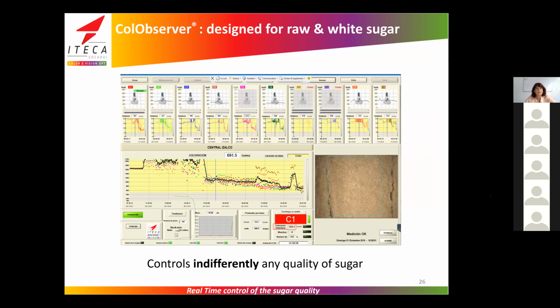The ColObserver is designed for raw and white sugar. We can configure different alarm thresholds and set points according to the sugar quality. For instance, we can set the correlation equation for each sugar quality with different range of color and use the one corresponding to the ongoing quality produced. In this case, C9 average color between 600 and 750 ICUMSA units could as well be 30 ICUMSA units and 1,500 ICUMSA units. Our ColObserver is a multi-products analyzer.